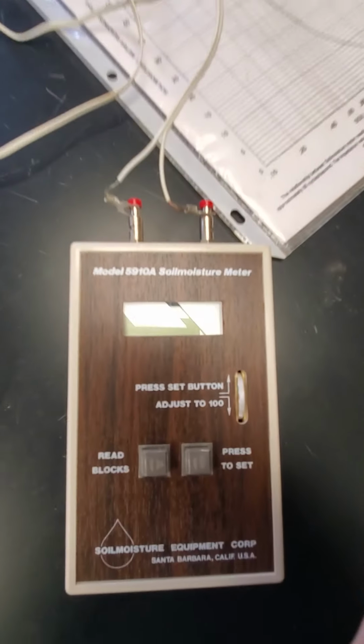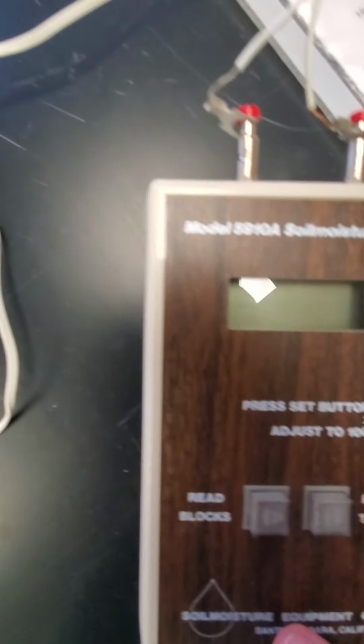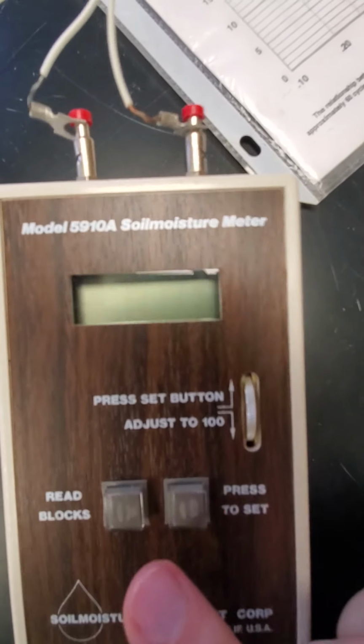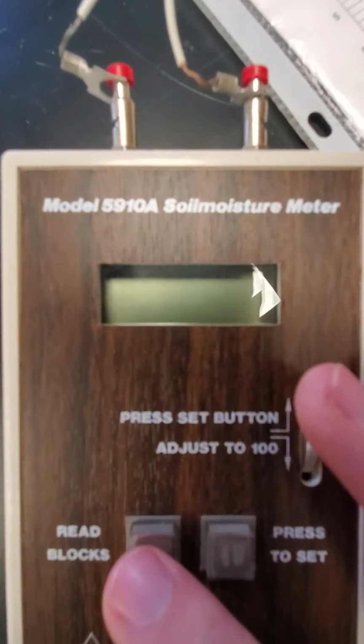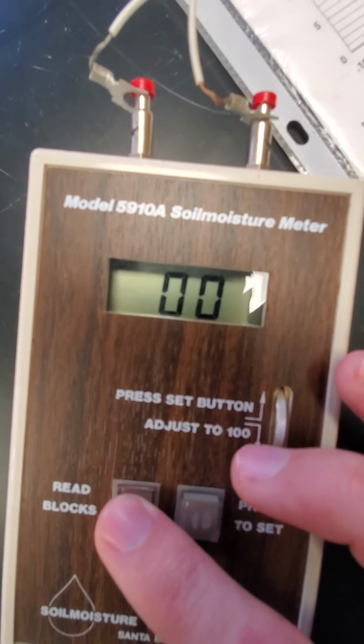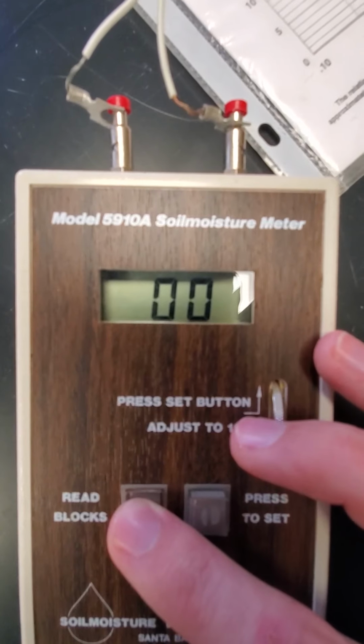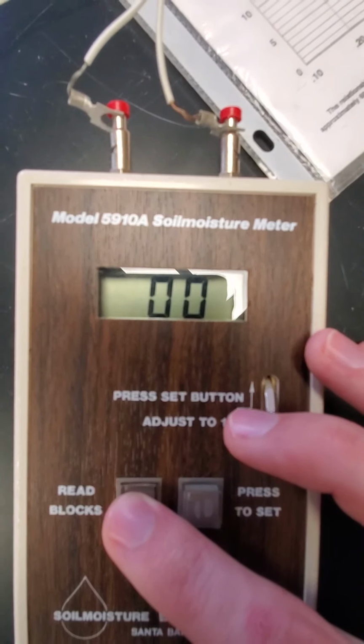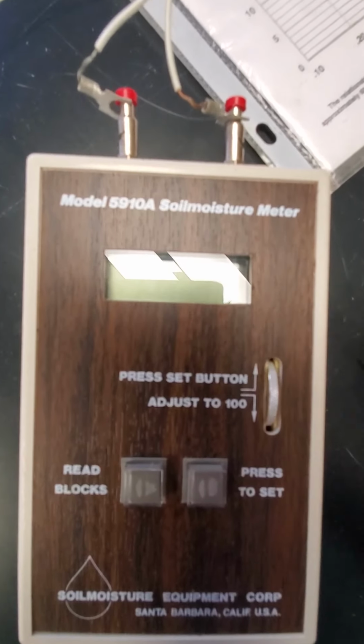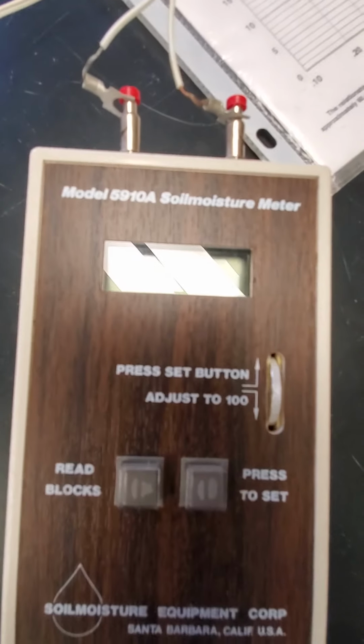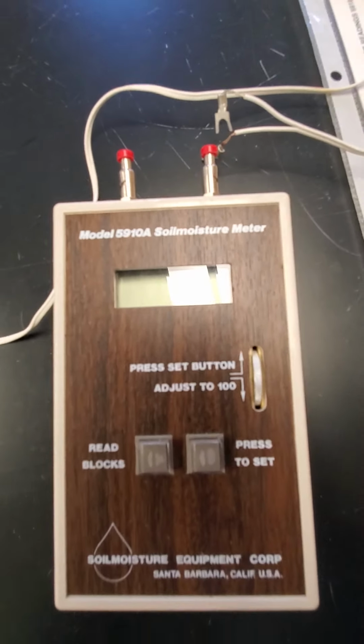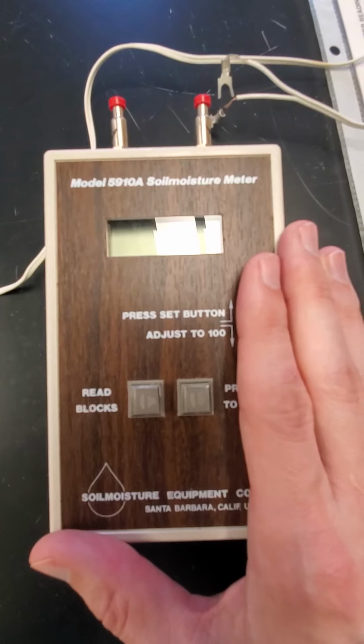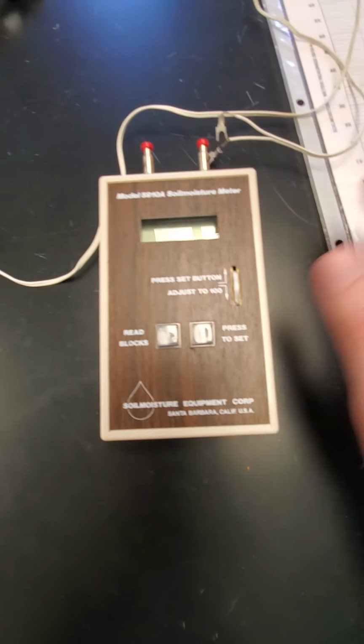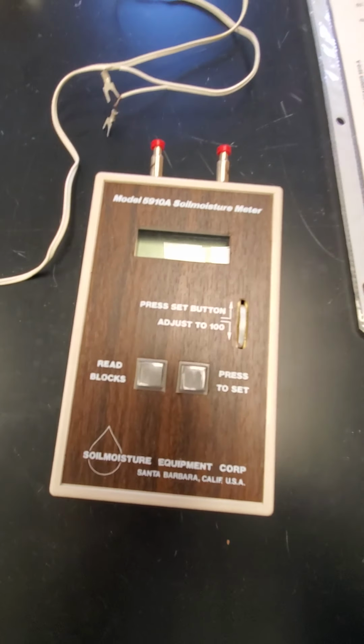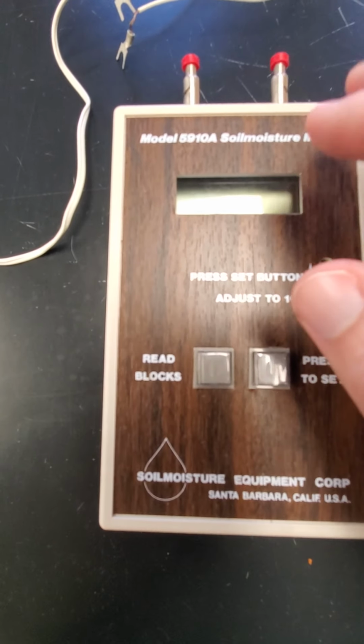So once you get those connected, you'll see that there's a readout here. And all we have to do is press the read blocks button to be able to see if there's anything there. Now, I don't have the gypsum in anything, so I don't actually know if we're going to get a readout. Let's see. Yeah, 0. Because there's full resistance, and we're not getting anything out of that. If it was completely water, it'd be something more, a higher number. But what this detector is doing is looking at resistance. So it's not actually looking at the water potential itself. So the number that we get out of here is just electrical resistance.